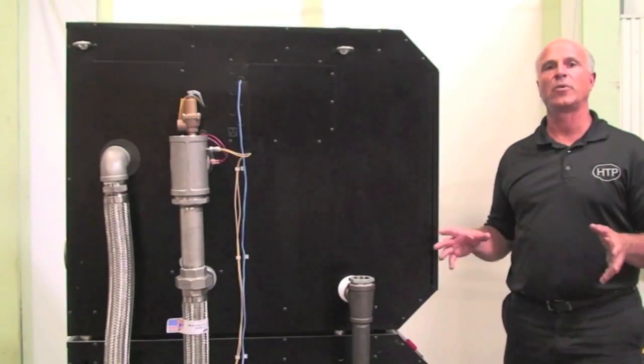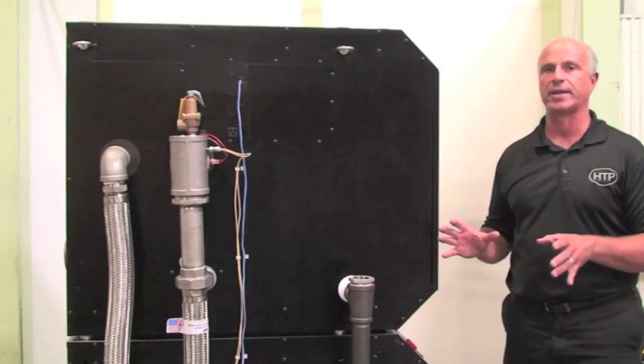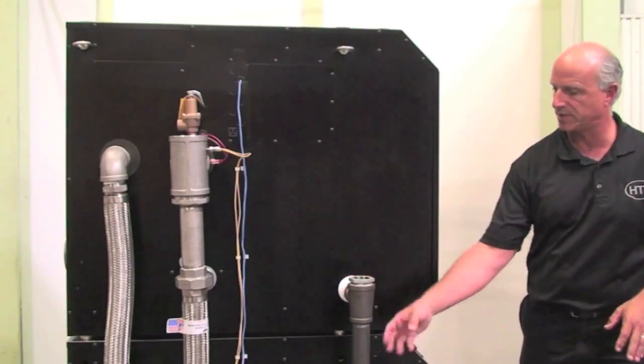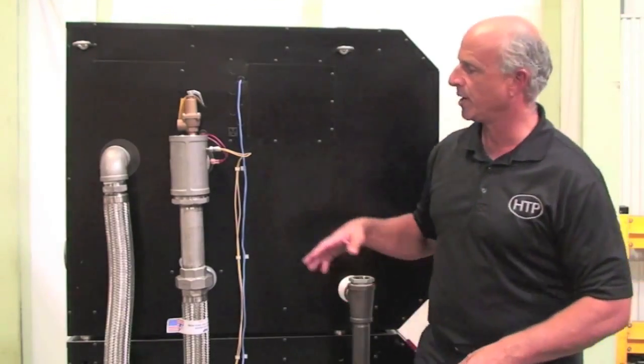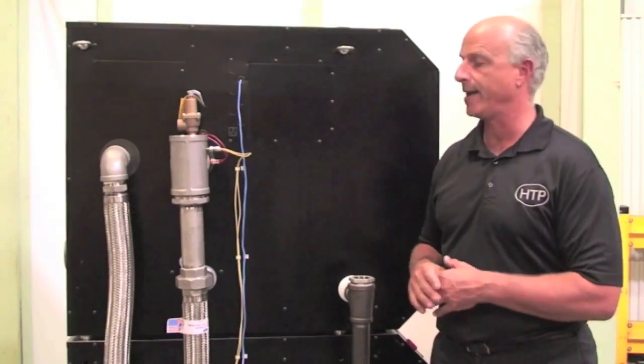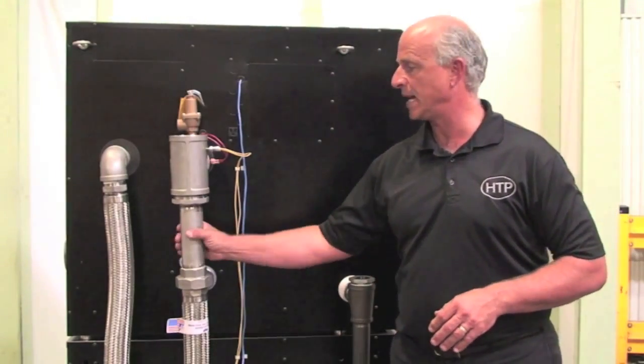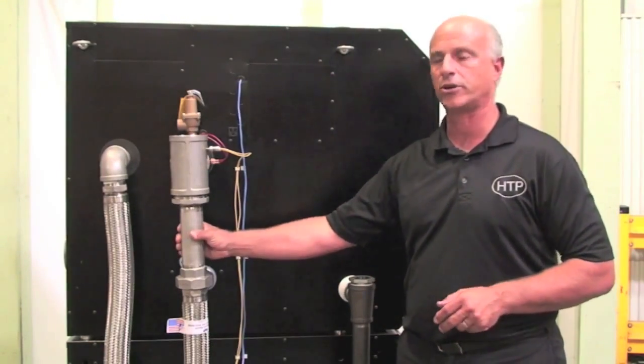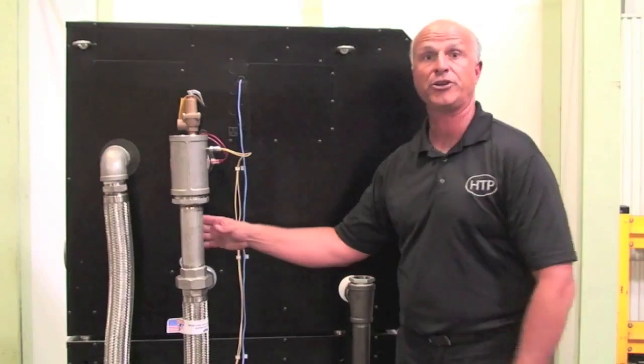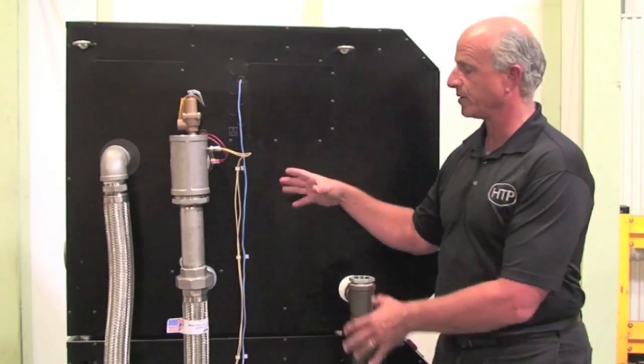The ModCon double stack - we've pre-piped everything, not only the gas piping as you can see here, but we've also done the return and supply piping. We've designed our piping so it's reverse return, so we get balanced flow through each module, each boiler, the top and the bottom.